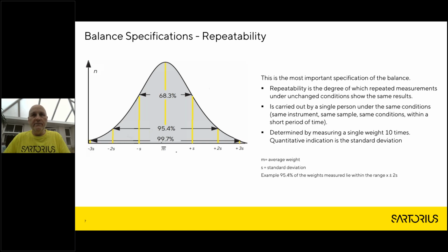From this standard deviation, we can tell how good the balance is. If you can see on this graphic, usually we're using a confidence of 2, which represents 95.4% of all measured weights, which should lie within that band you can see on that graphic. So repeatability is one of the most important specifications that tells you the quality of the balance and how good it is at giving you correct results.